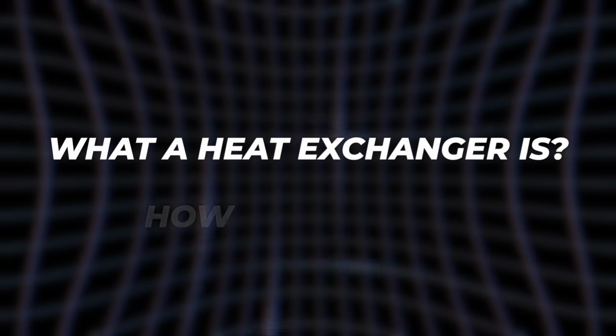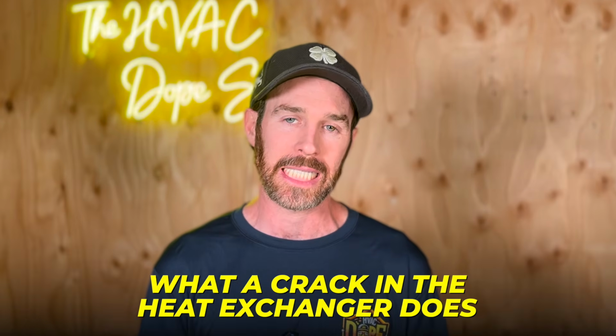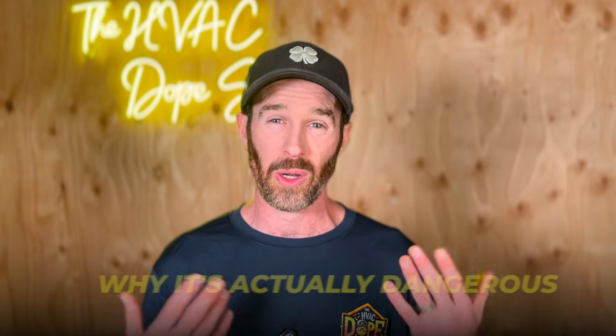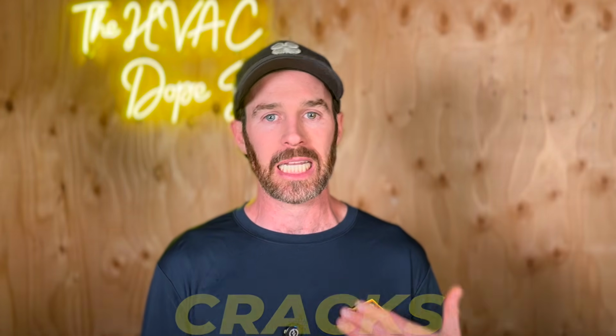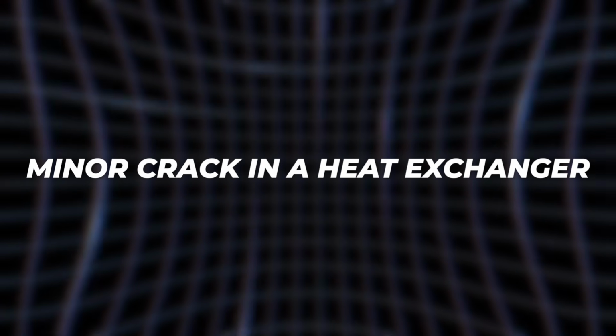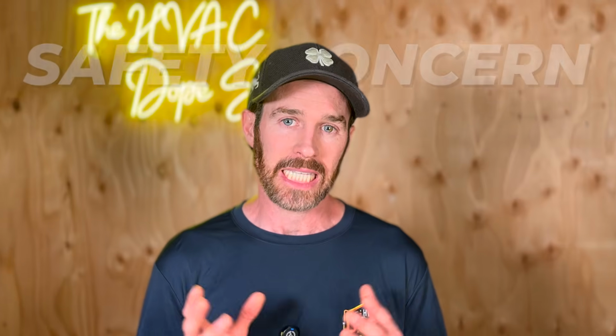Now, the reason I like to start with the explanation of what a heat exchanger is and how it works is so that you can visually understand what a crack in the heat exchanger does and what the implications are and why it's actually dangerous. And I'm going to talk about to what extent it is dangerous. Because the truth is there's varying levels of cracks, but even if we find a very minor crack in a heat exchanger, unfortunately, it is something that is considered a safety risk. And so from a liability perspective, we're always going to recommend that you deal with it. It's not something that we can leave unattended because it is a safety concern.